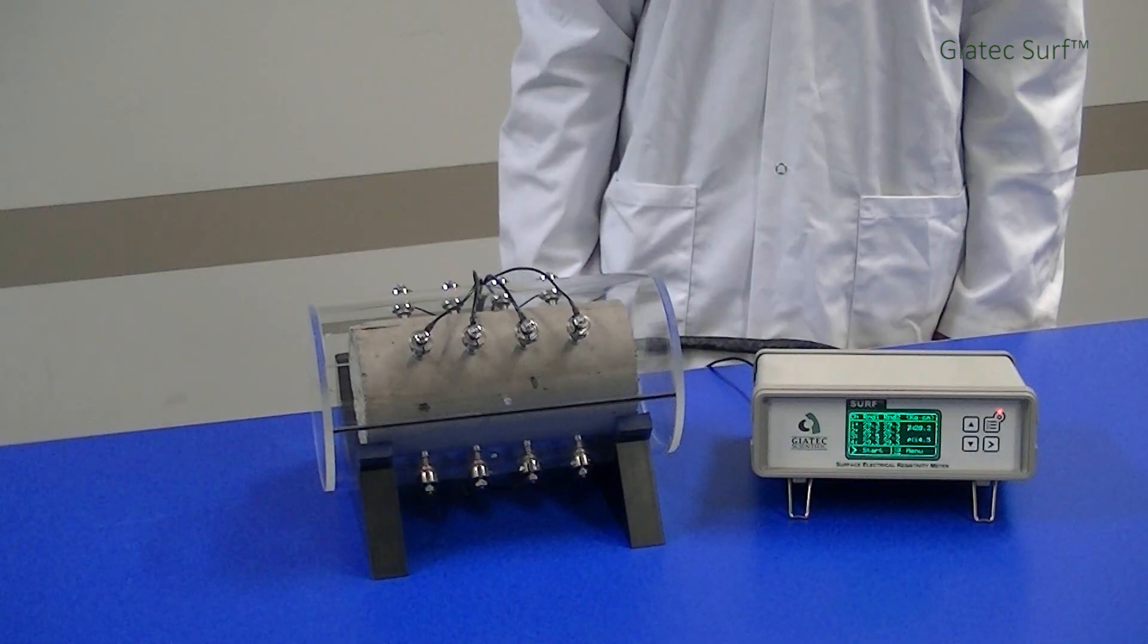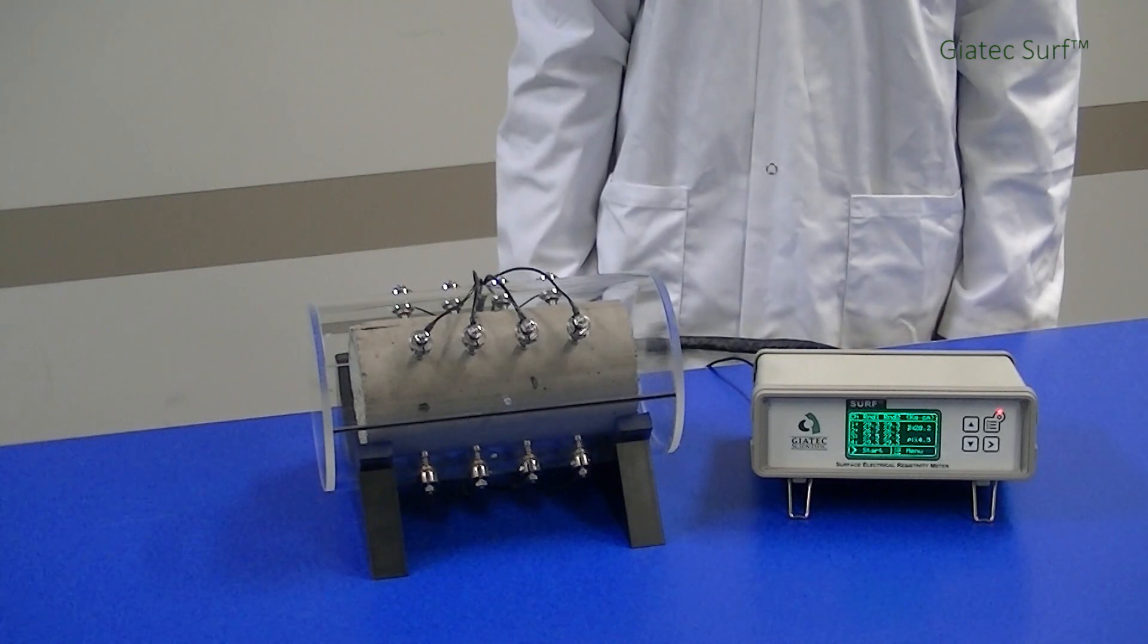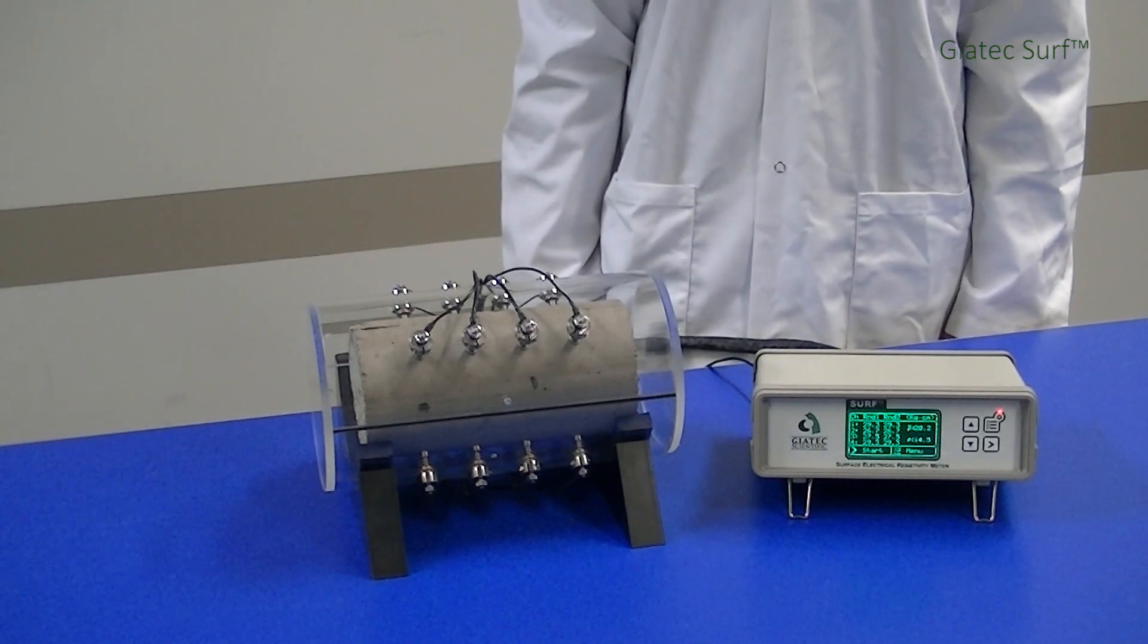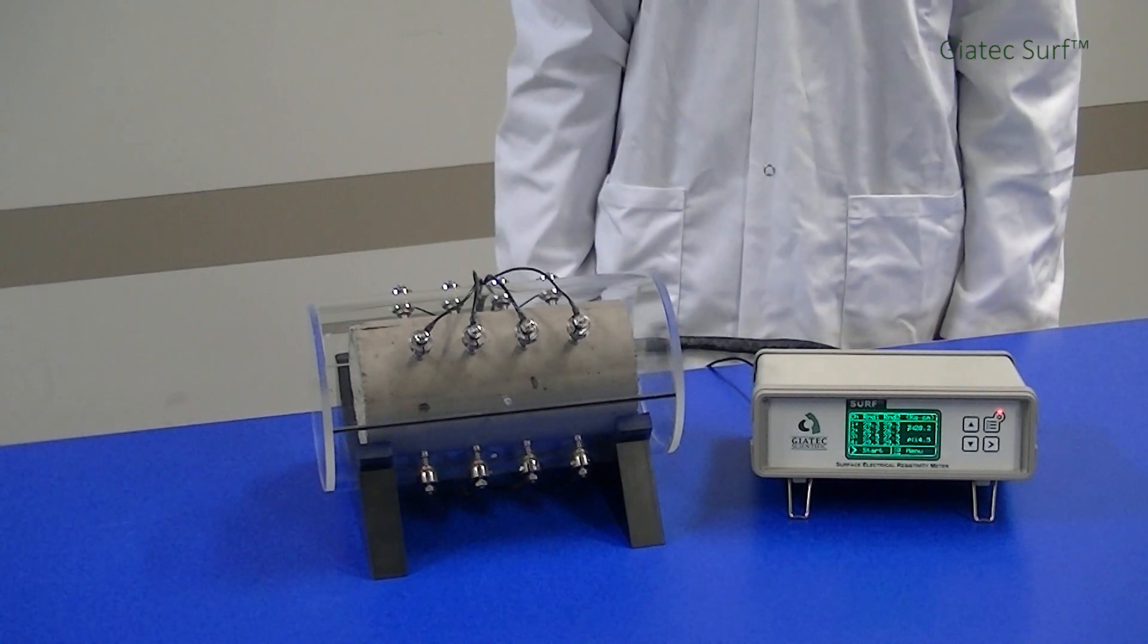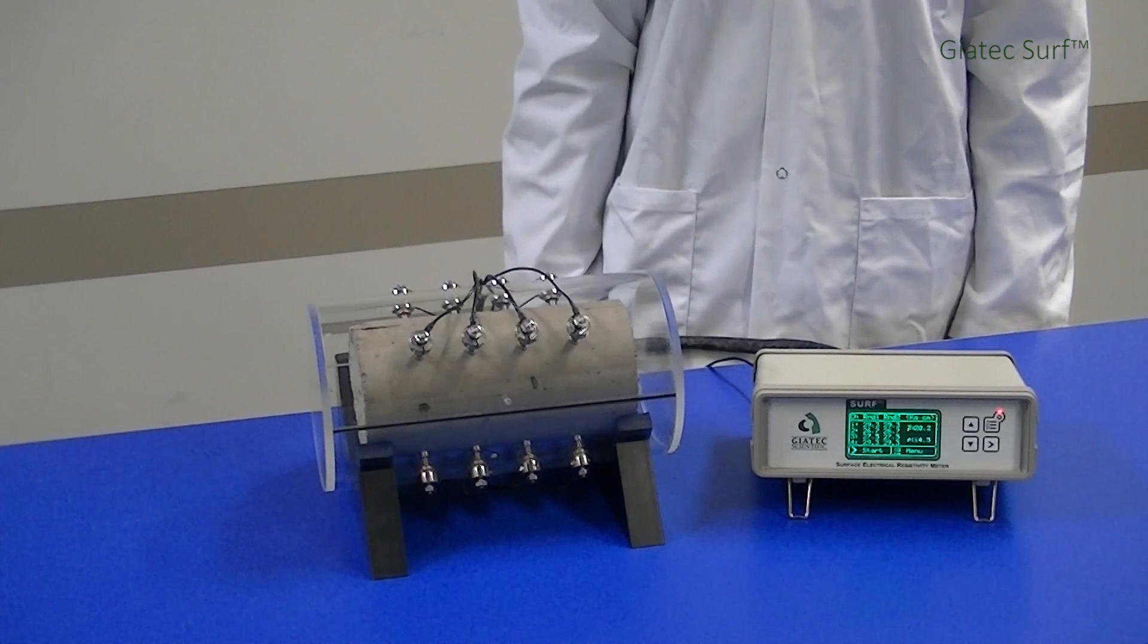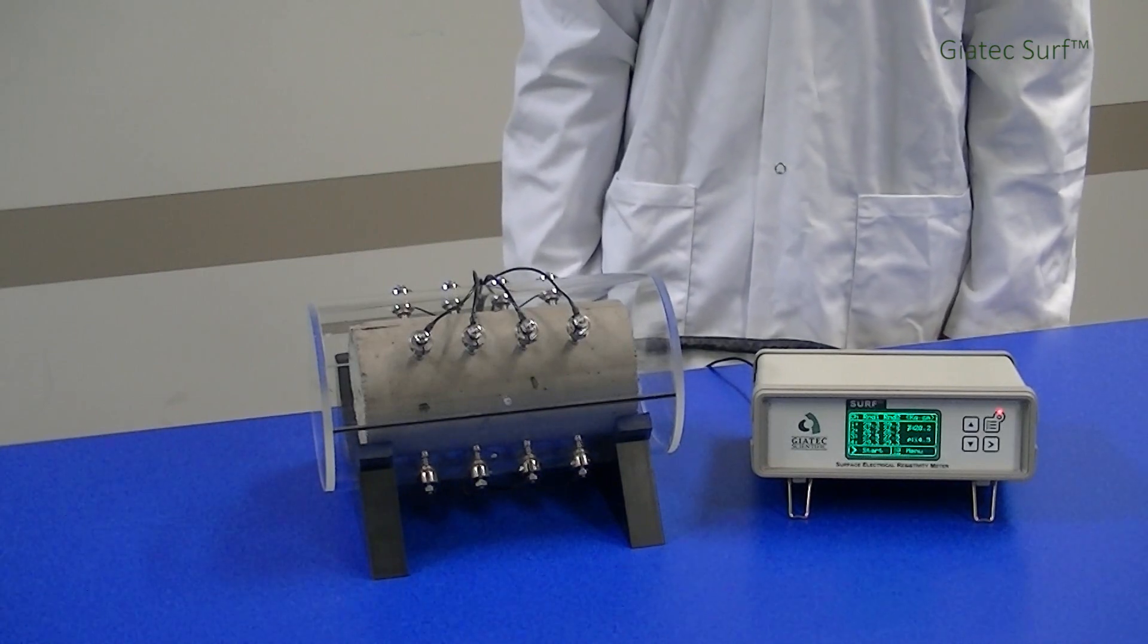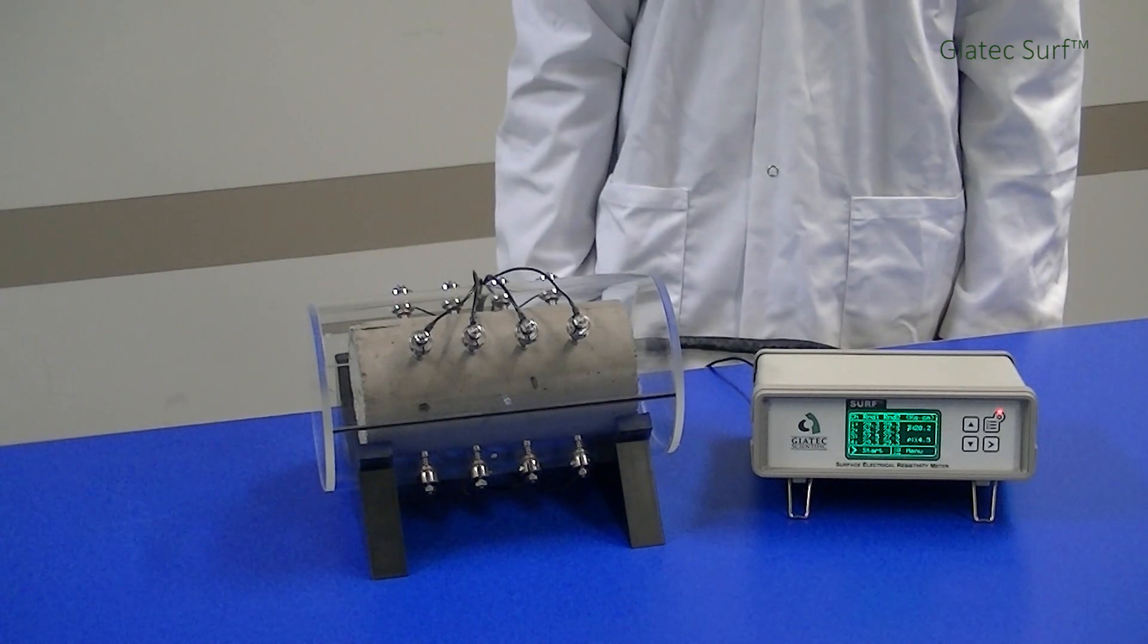For more information regarding test setup, please see the device setup section of the SURF user manual. I should mention that data logging can be carried out with the Giatec SURF data monitoring PC software using the USB connection. The software provides full control over the device. It can also generate report files that are compatible with the guidelines of ASTM and AASHTO. Thank you for watching this video.